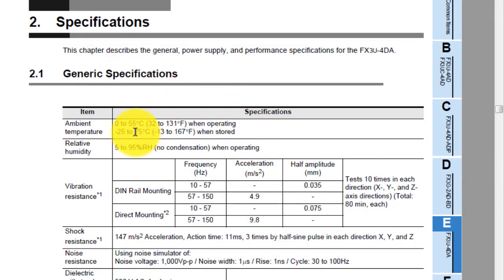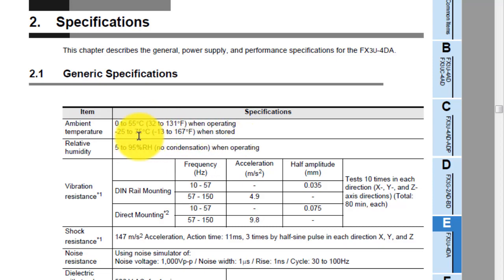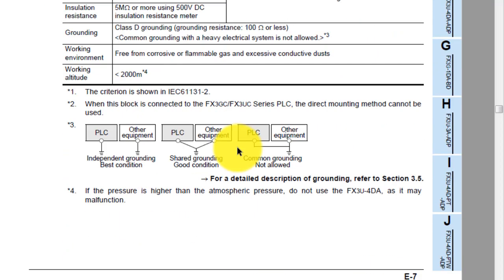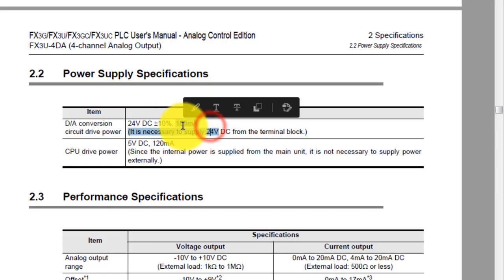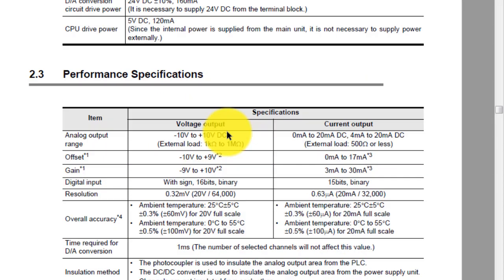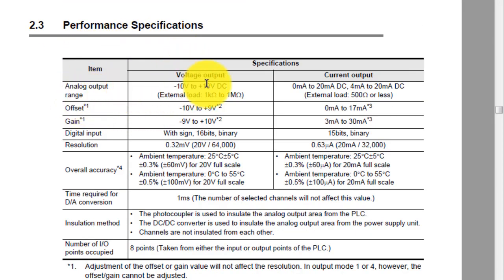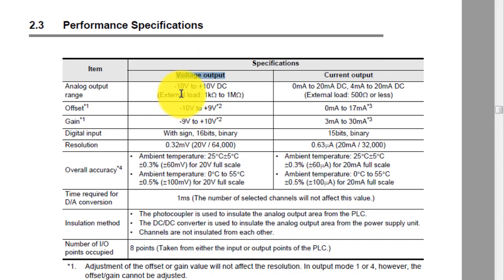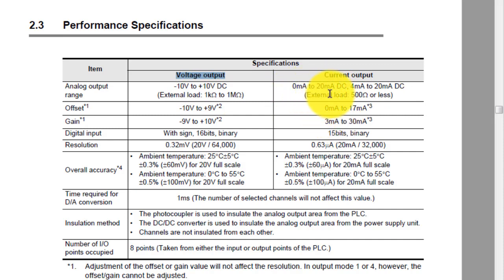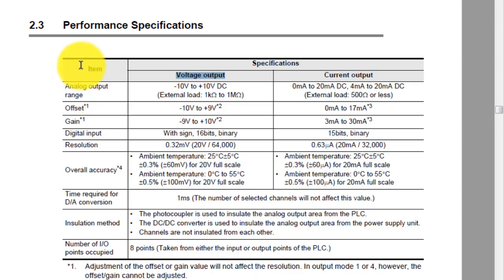This is the specification of the FX3U-4DA module, including ambient temperature, operating temperature, and storing temperature. For power specification, you have to use 24V DC and it will use 160 milliamperes in operating mode. The analog output range includes voltage output from minus 10V to plus 10V, and current output in two options: 0mA to 20mA, or 4mA to 20mA.